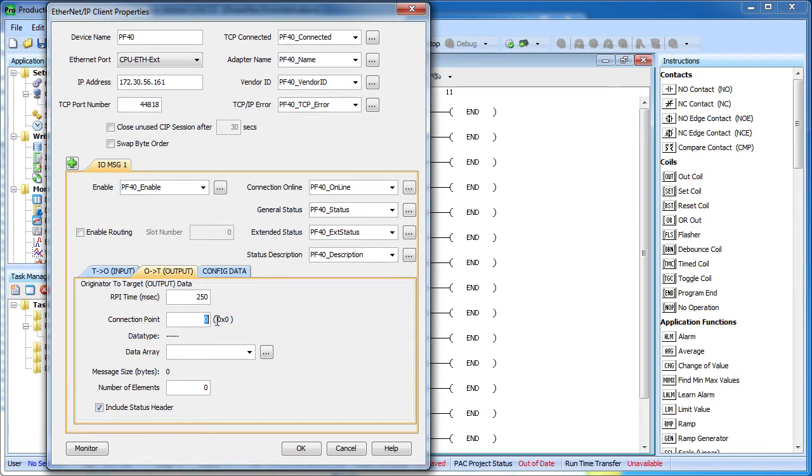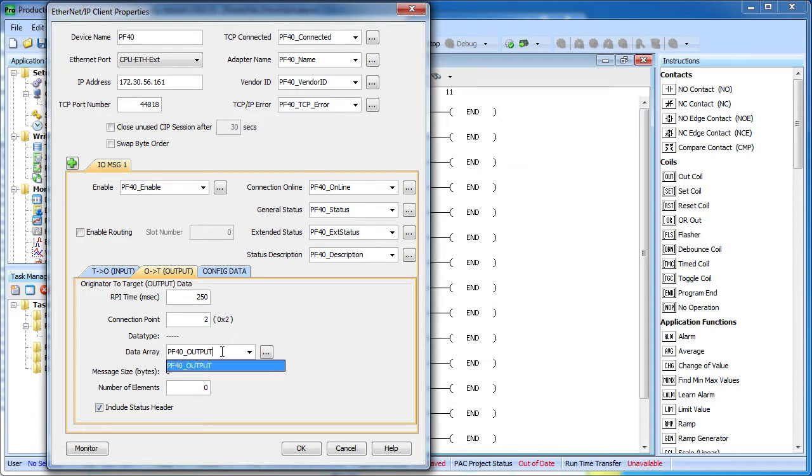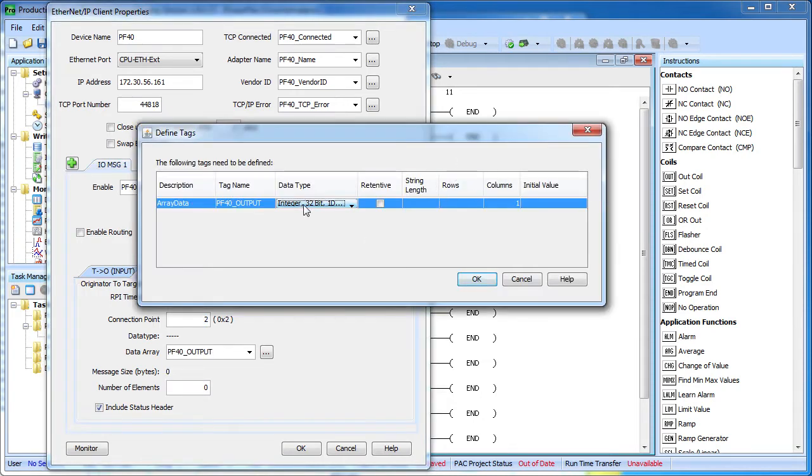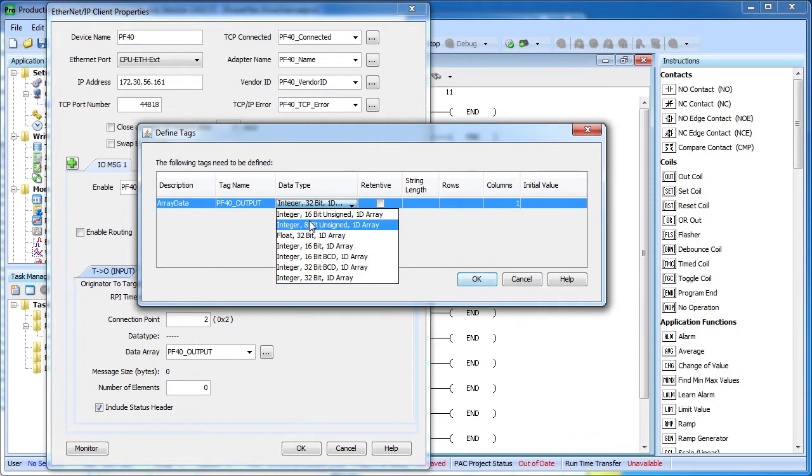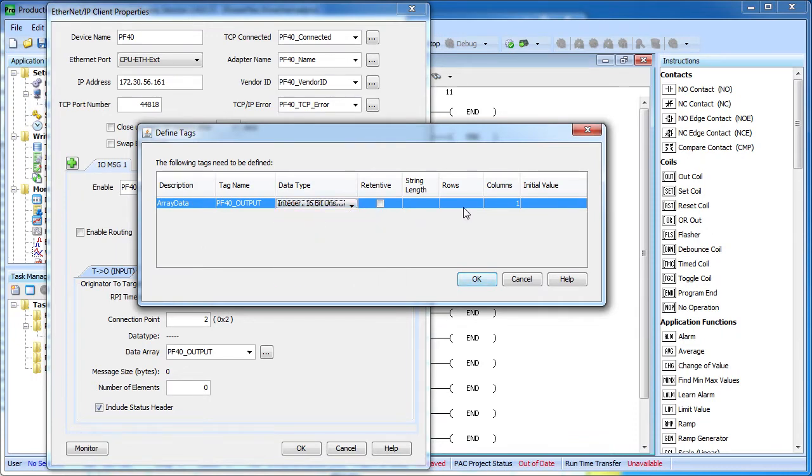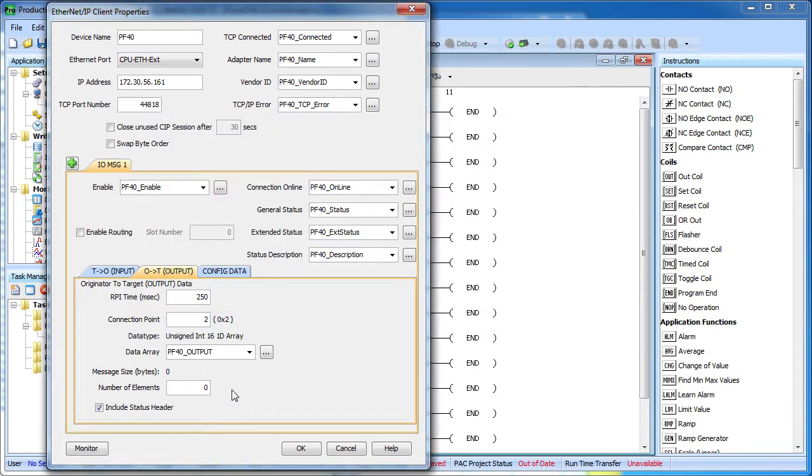The connection point for the output data, or assembly instance as they refer to it in the drive documentation, is a 2. We need to create an array of output data that the Ethernet IP protocol can send down to the drive. And according to the documentation for the drive, those need to be 16 bit integers and it can be up to 10 of those, again depending on the drive configuration. For our setup with only a single drive, we only need to send 2 of those elements.